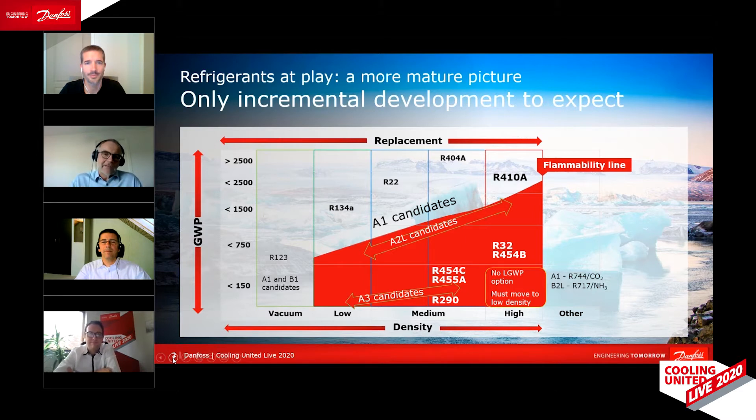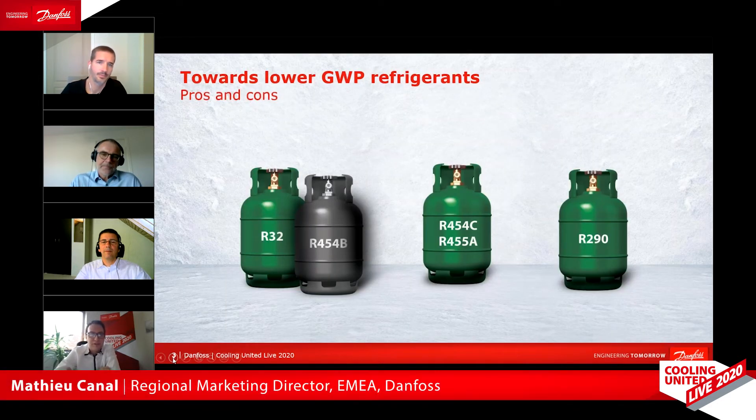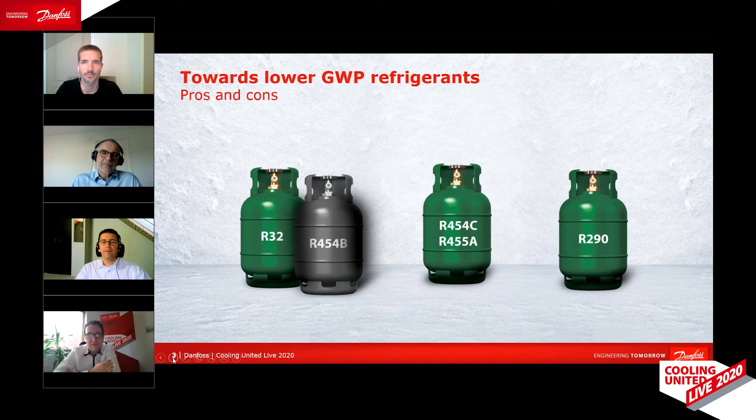The current market of heat pumps is using R410A as a refrigerant. R410A, like all high-density refrigerants, brings advantages in unit design. Thanks to the refrigerant properties, OEMs were able to reduce unit costs versus the legacy R407C and R134A by downsizing the piping, compressor, and heat exchanger, making the heat pump more financially attractive. Efficiency is also a key driver, and the natural efficiency of high heat-density refrigerants helped increase the overall performance of the unit. Considering the uncertainty of the refrigerant future, a natural move for heat pumps would be to go to the next high-density alternatives: R32 or R454B.